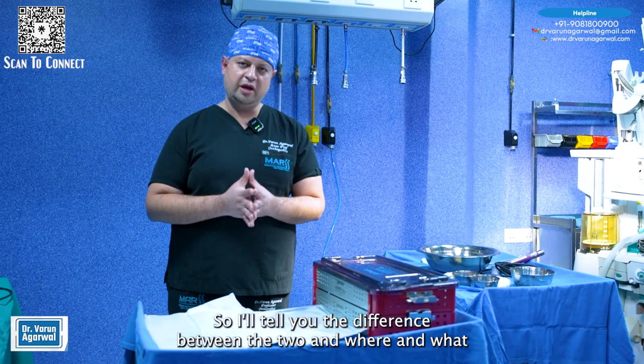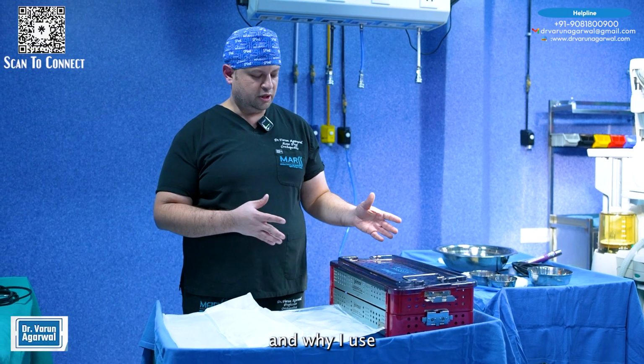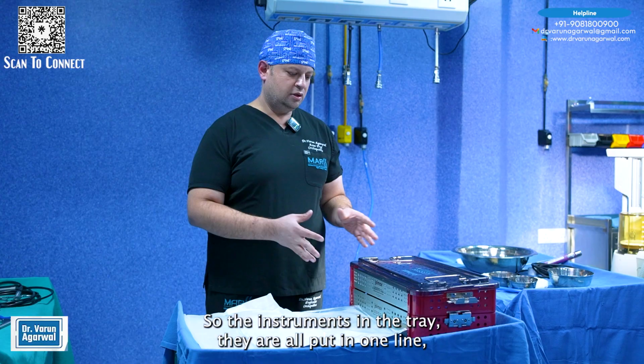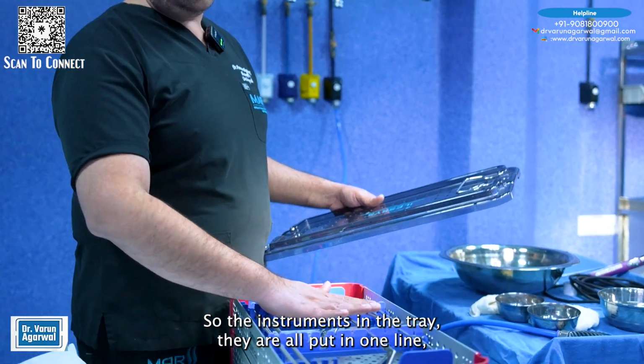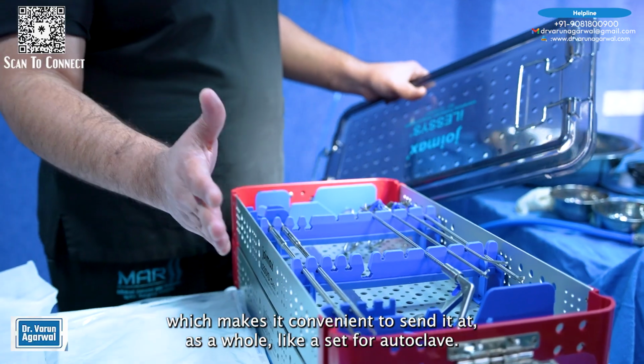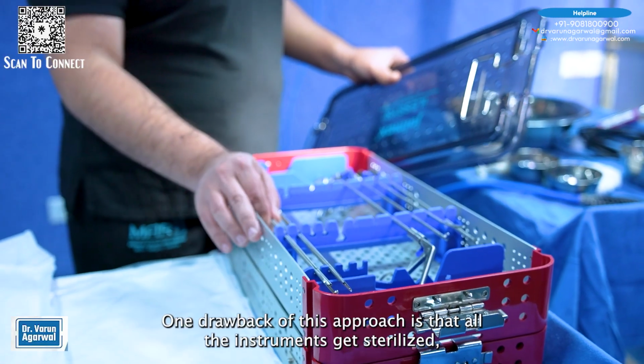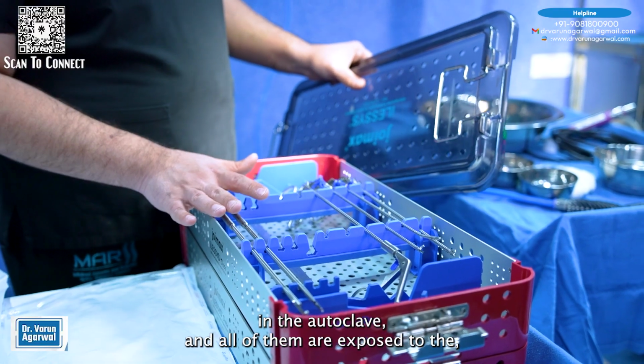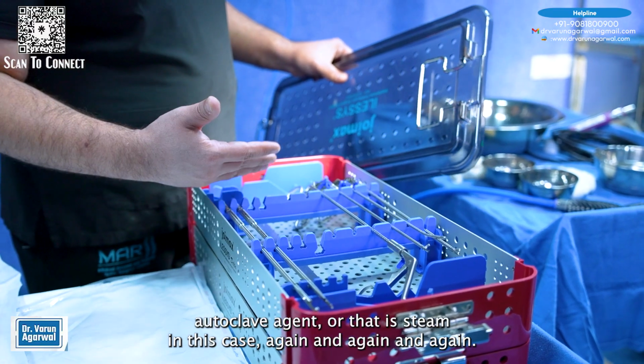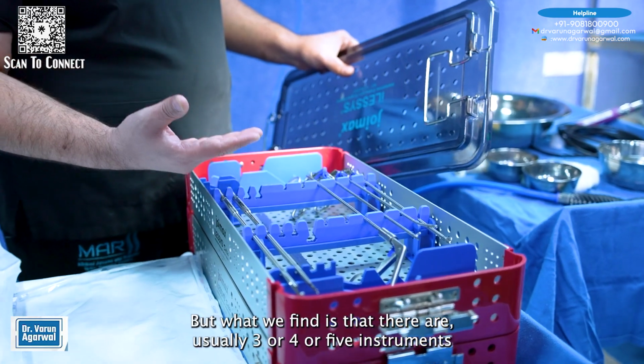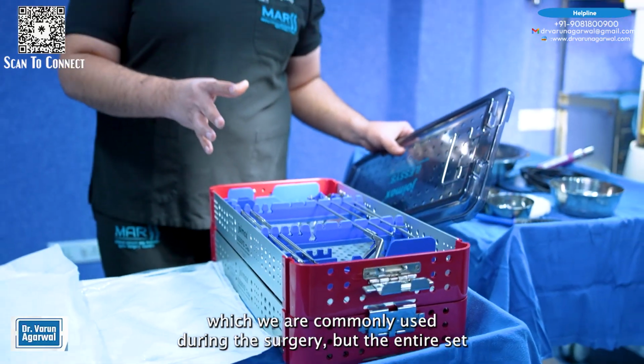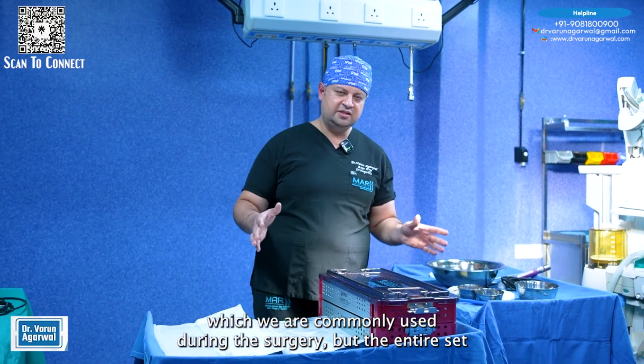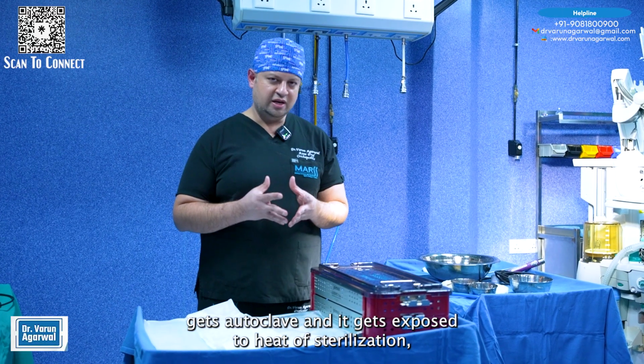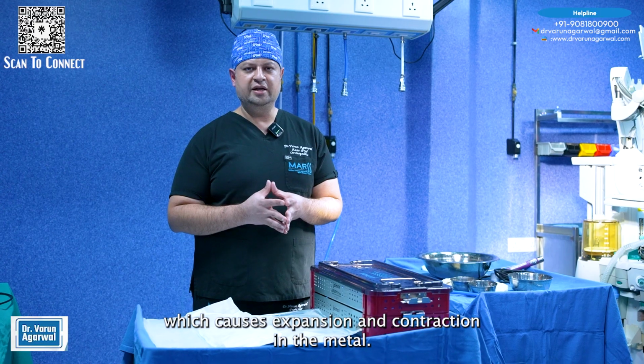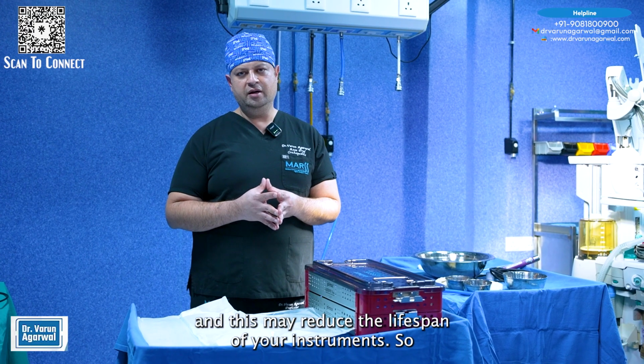So I'll tell you the difference between the two and where and why I use a tray and where I use a peel pack. The instruments in the tray are all put in one line, which makes it convenient to send it as a whole, like a set, for autoclaving. One drawback of this approach is that all the instruments get sterilized in the autoclave, and all of them are exposed to the autoclaving agent, that is steam in this case, again and again and again. But what we find is that there are usually 3 or 4 or 5 instruments which are commonly used during the surgery, but the entire set gets autoclaved and exposed to heat of sterilization, which causes expansion and contraction in the metal, and over a period of time it weakens the metal, and this may reduce the lifespan of your instruments.